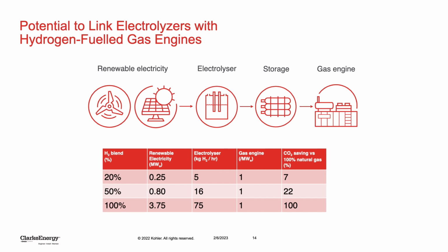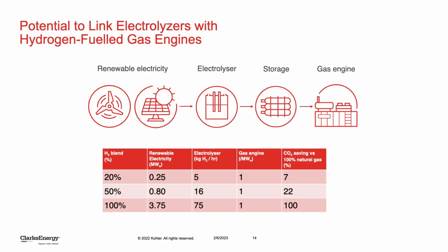From a hydrogen blend perspective of 20%, as we discussed before, the renewable electricity you'll need to run that will be around about 0.25 megawatt. The electrolyzer will generate 5 kilograms of hydrogen per hour, and that will support a 1 megawatt gas engine. If you want to go all the way to a 100% hydrogen blend and achieve that full decarbonization, you'll need 3.75 megawatts of electricity, along with an electrolyzer generating 75 kilograms an hour of hydrogen.